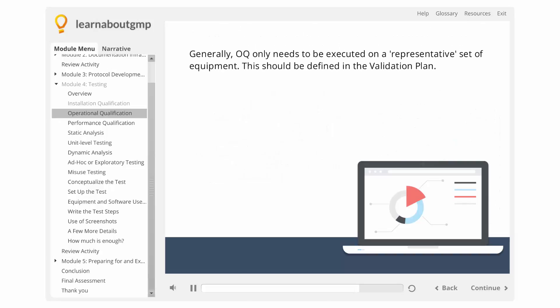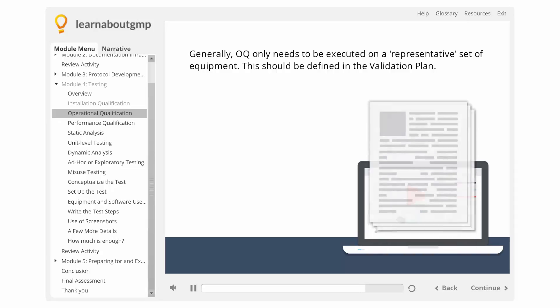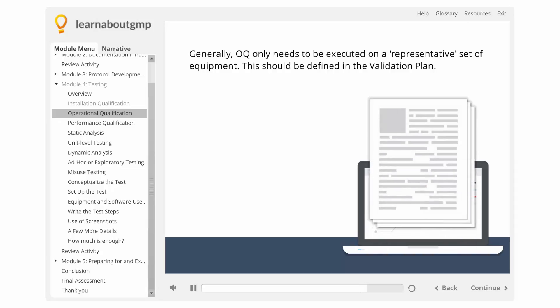Generally, OQ only needs to be executed on a representative set of equipment. This should be defined in the validation plan.